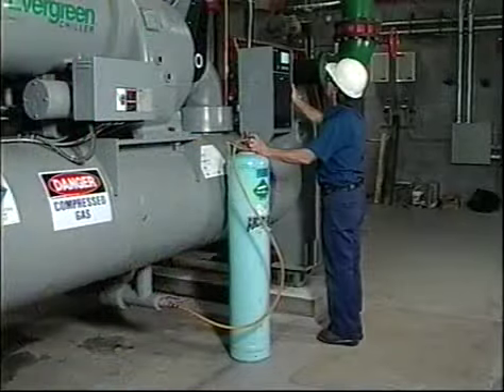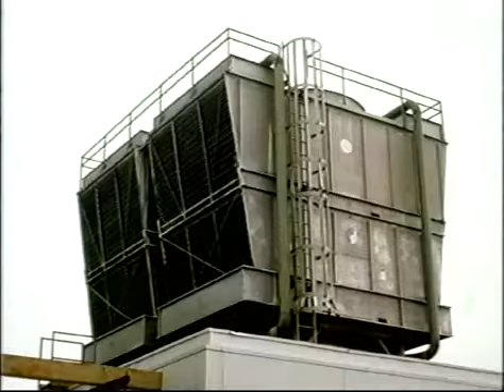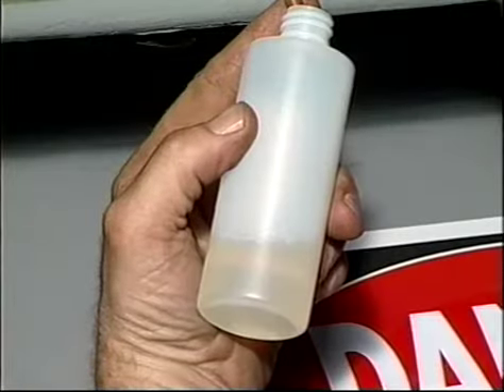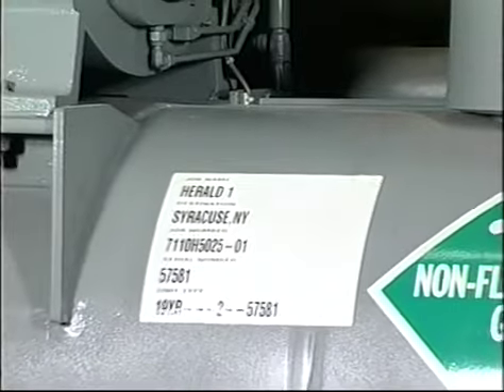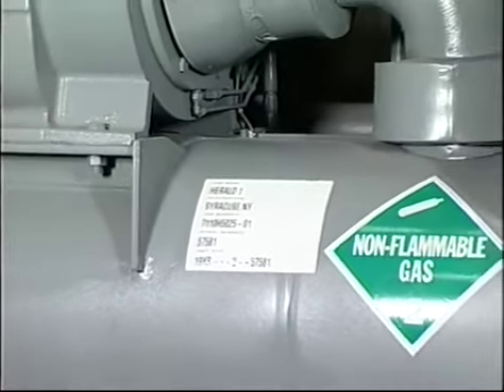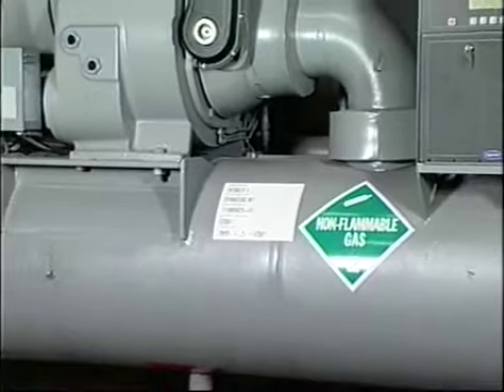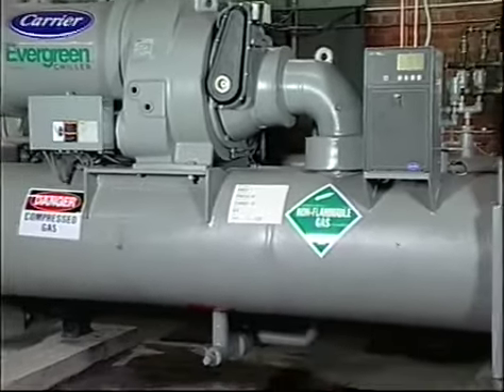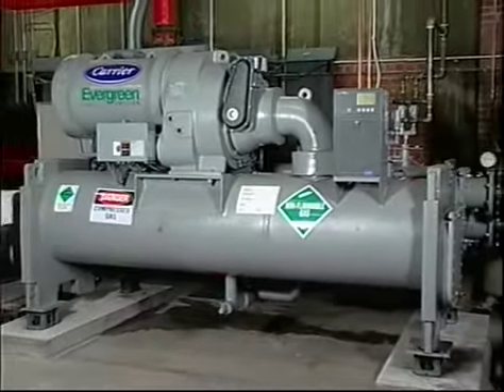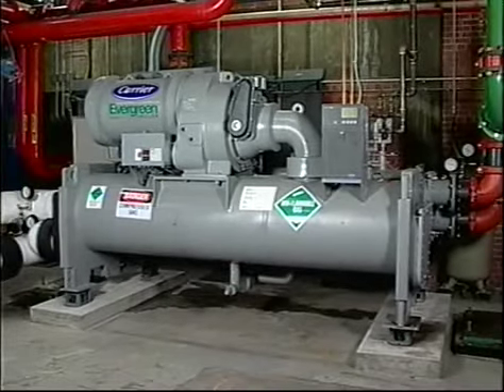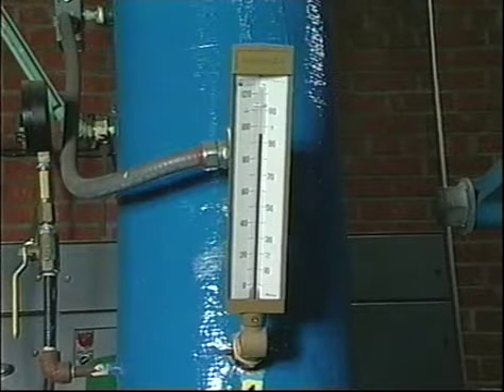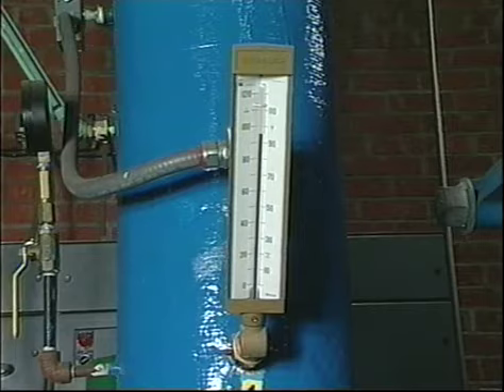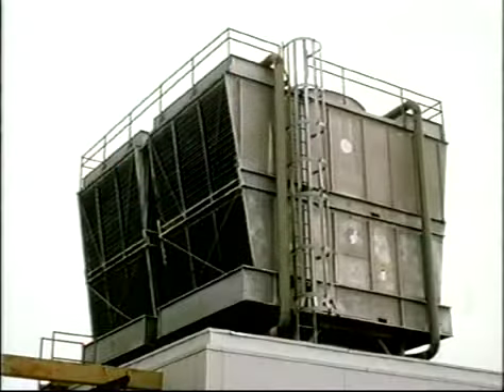Remember that if the critical balances of refrigerant, water, oil, and air are maintained, improved efficiency and cost savings will be realized. These result from lower power requirements and the prevention of unexpected major failures. Basically, the aim is to keep the condenser head pressure requirements within equipment specifications. This will result in the lowest possible kilowatt requirements.